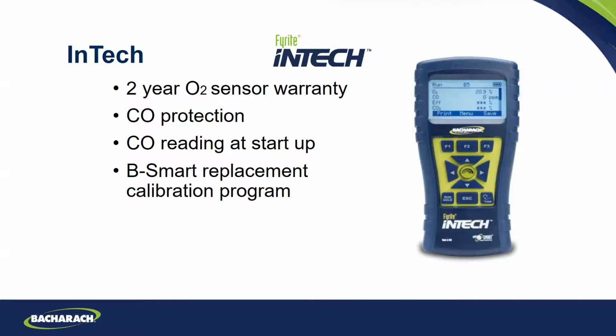and that just kind of freaks a lot of people out. So what all manufacturers do is we say there's no CO here, this is 0. So you turn this on, it calibrates the oxygen sensor and zeros the CO sensor. That's fine, except the problem may be there's CO in the building you're in. Say there's 10 ppm of CO in the building and you turn this on and it zeros to it. Now when you see 10 ppm in a flue, it's going to read 0. If you see 20 ppm in that flue, it's really only going to read 10. So you're going to be off by whatever it zeros to. What if it was 30 ppm in that building? Now you're off by 30 parts per million.